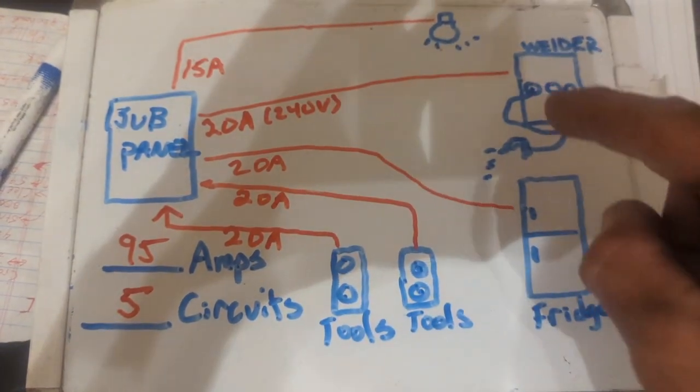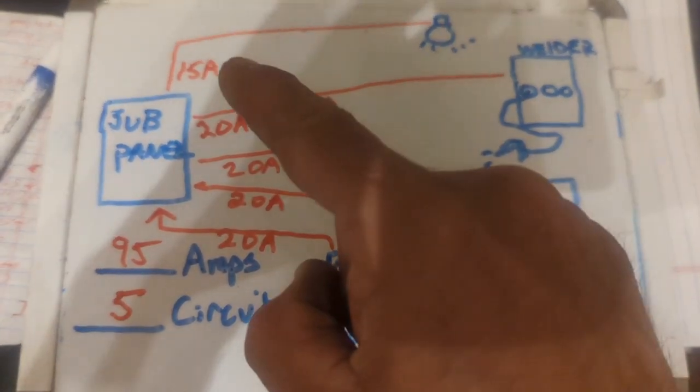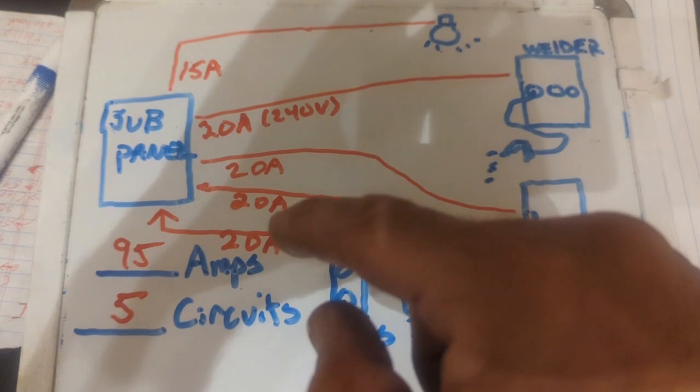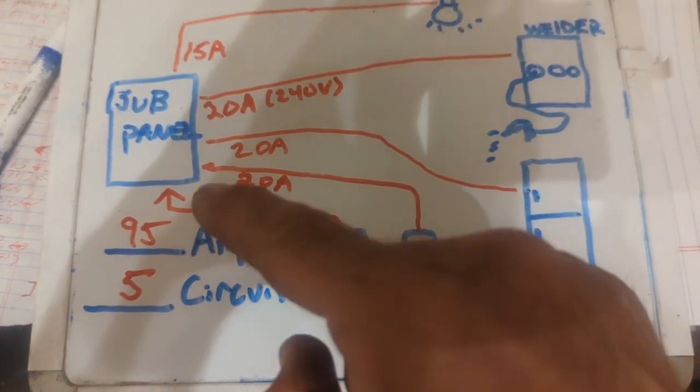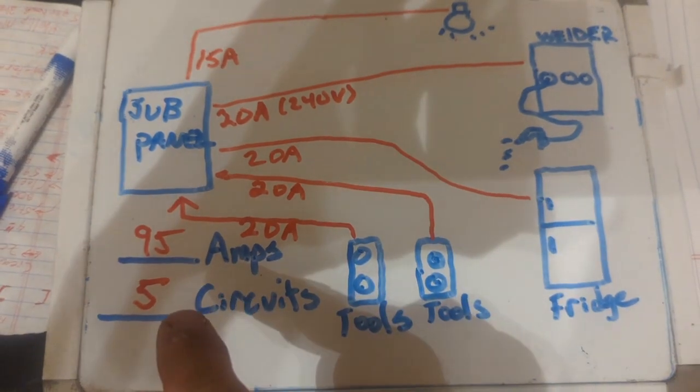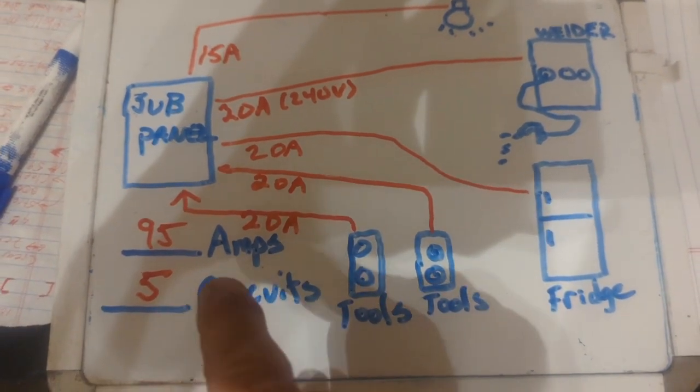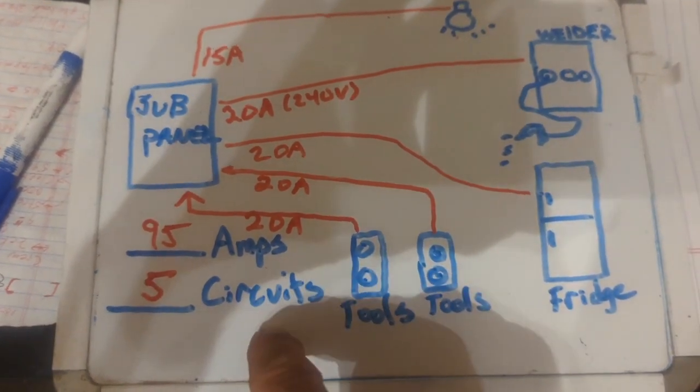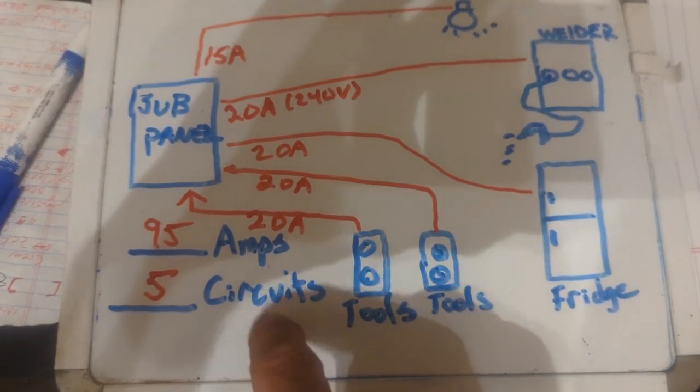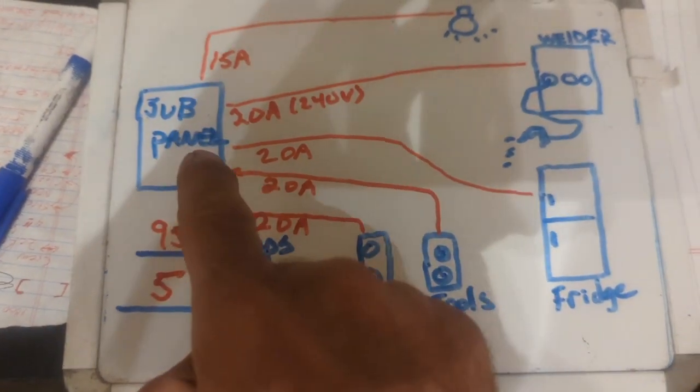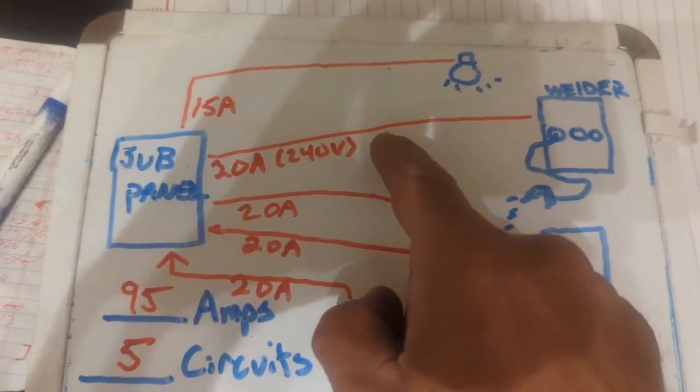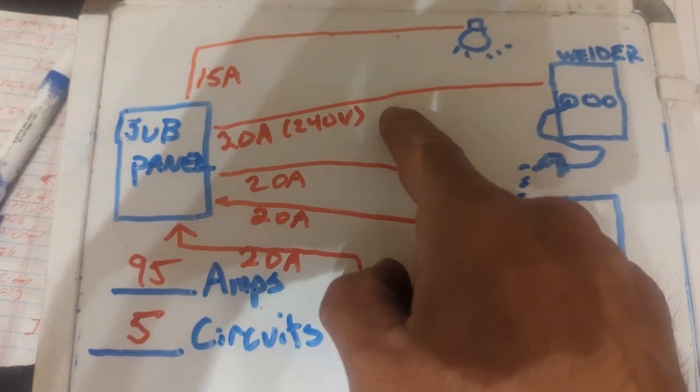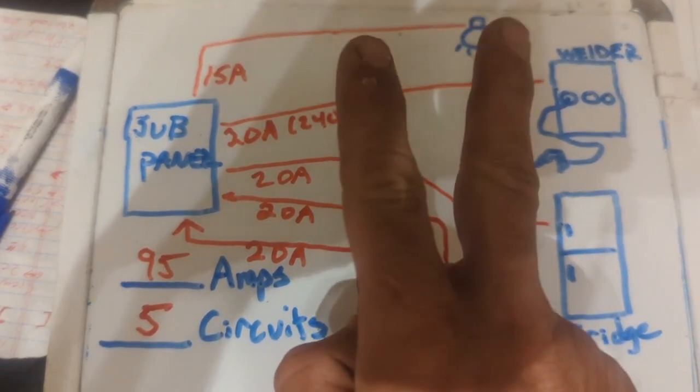So what I do is I simply will add up the amperage on these breakers. Not how much you're using on these, but how much the breakers are going to be. So the breakers I determined there's going to be 95 amps on the breakers and five circuits. Now this is wrong because if I went by this, the box that I got would be too small because this welder is going to be using a double pole breaker, meaning it's going to take up two slots.